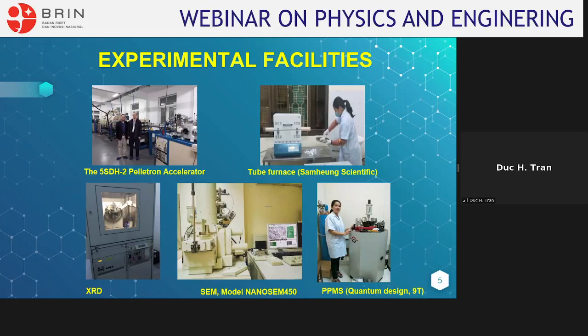And from last year, we restarted the new PPMS Quantum Design system, with field up to 9 Tesla and temperature down to 4.2 Kelvin. And we use a closed cycle liquefier, so we don't need to worry about liquid helium, as Uta and I experienced in Korea. Now we can do experiments anytime. So after this talk, I would like to get some collaboration with all of you, especially on sample characterization.